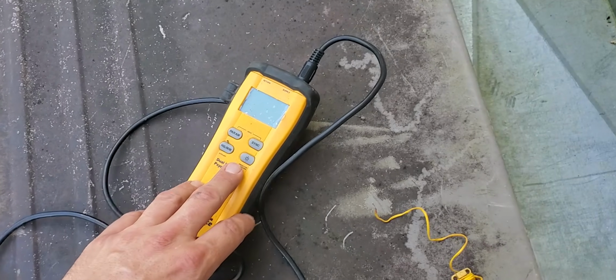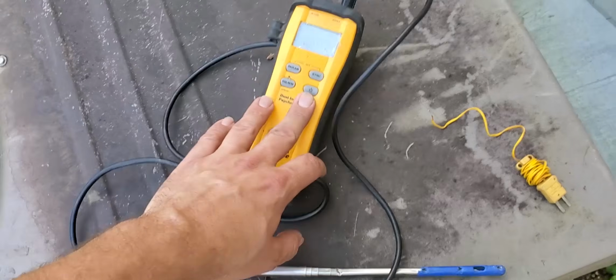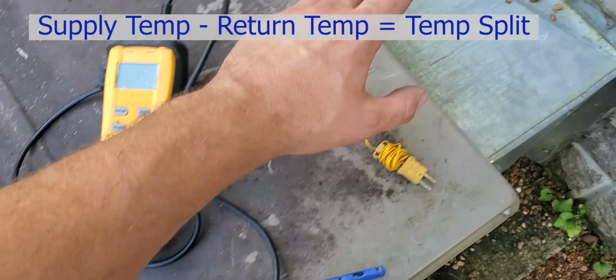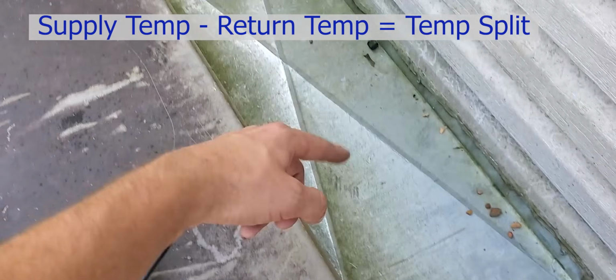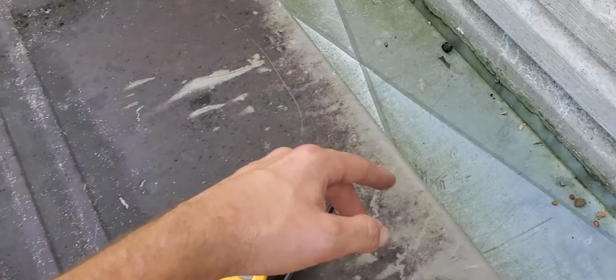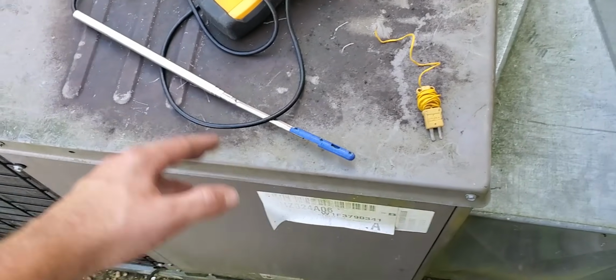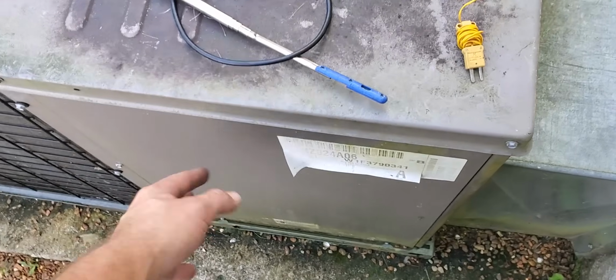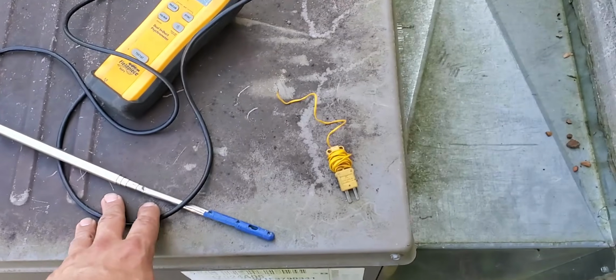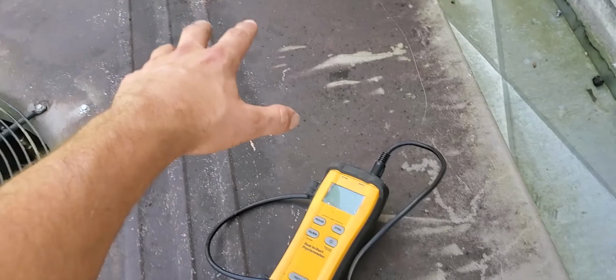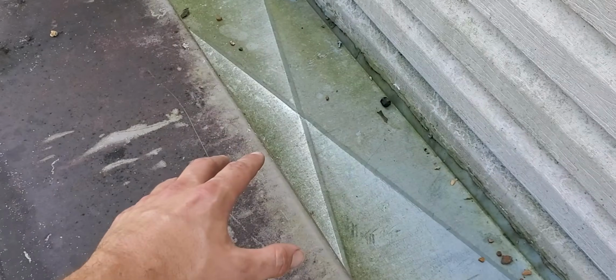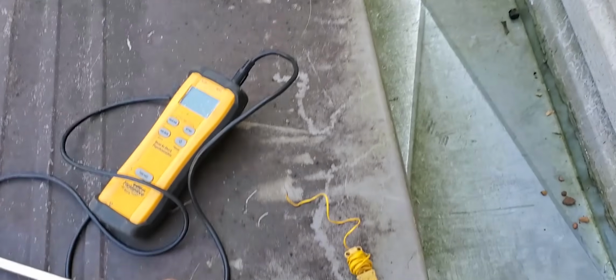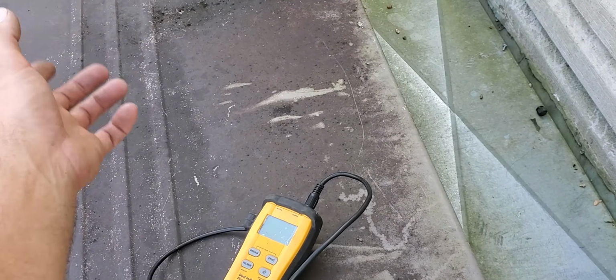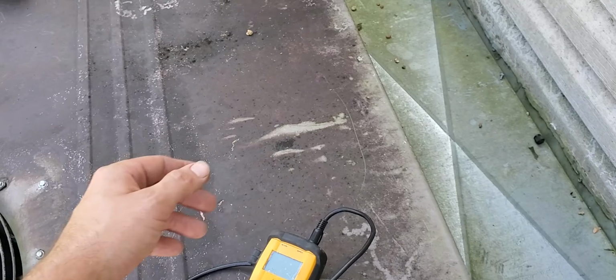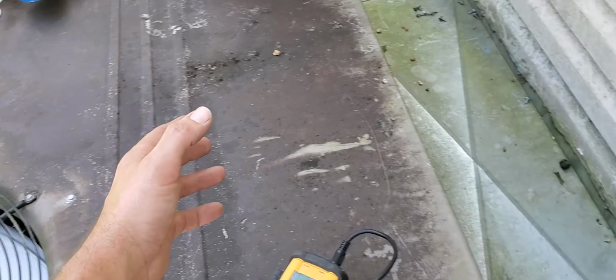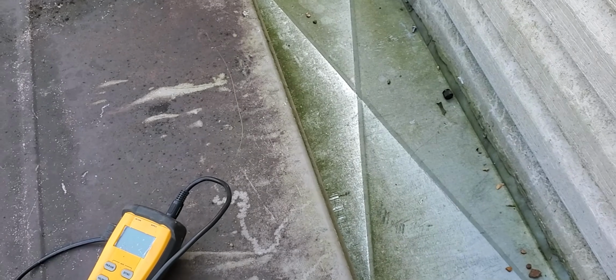While you're checking your superheat and your subcooling, use a temperature probe in the duct. That way you can measure the temperature split between return and supply. You want around 20 degrees on this residential package unit here. This is where the blower is. Blower speed is going to affect the amount of airflow on the coil and therefore affect the temperature split. So if you raise the fan speed one step, from low to medium or medium to high, then you could lose a couple degrees in your airstream here for your temperature split.